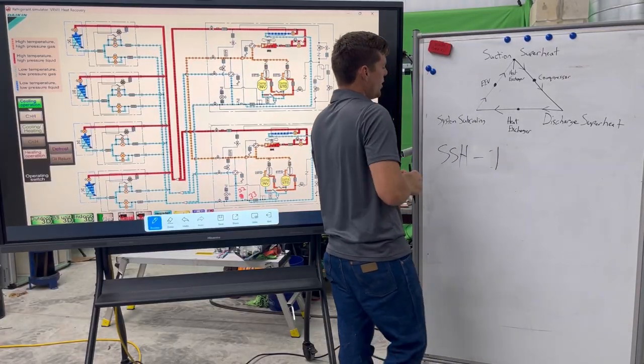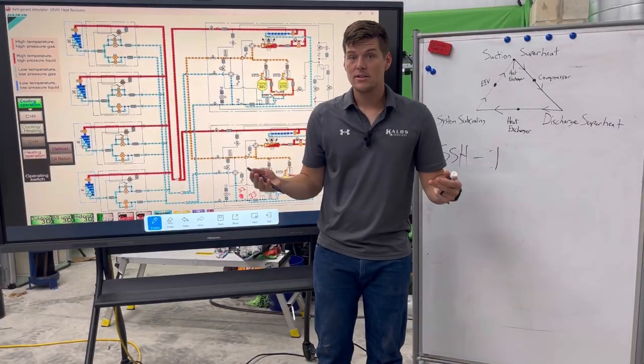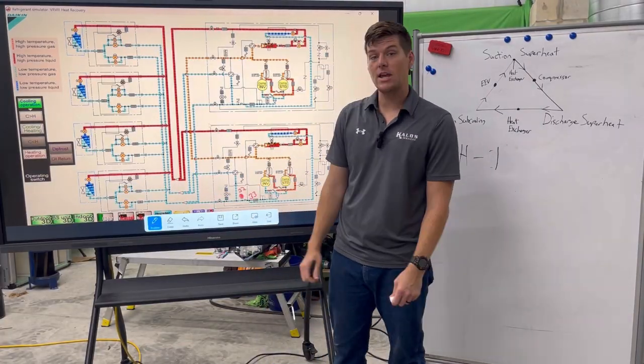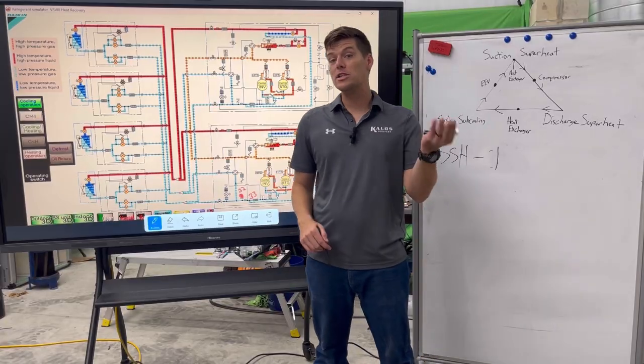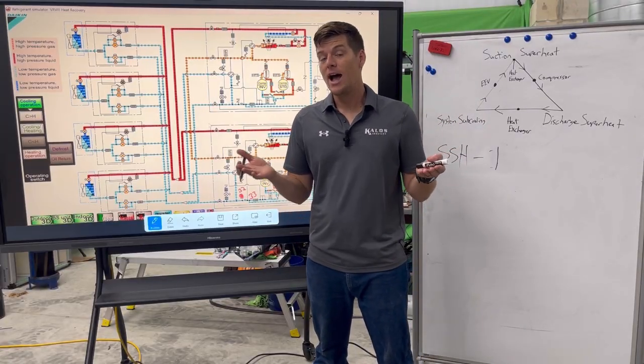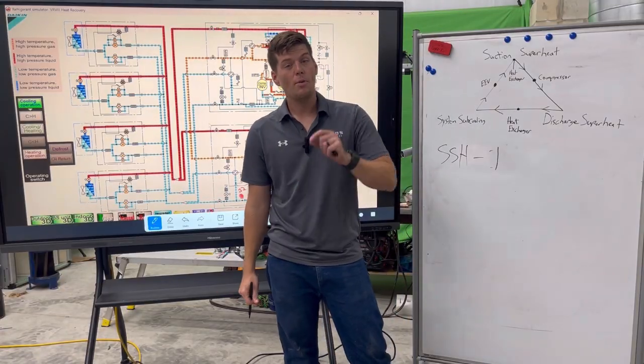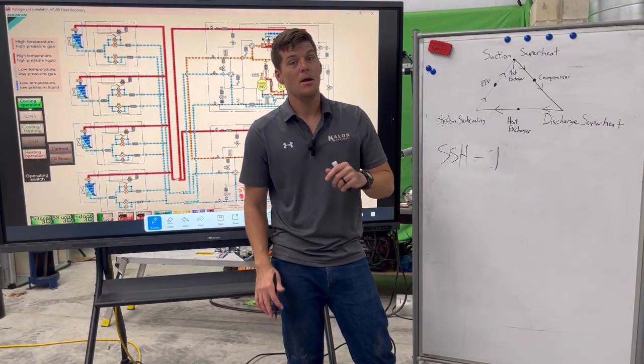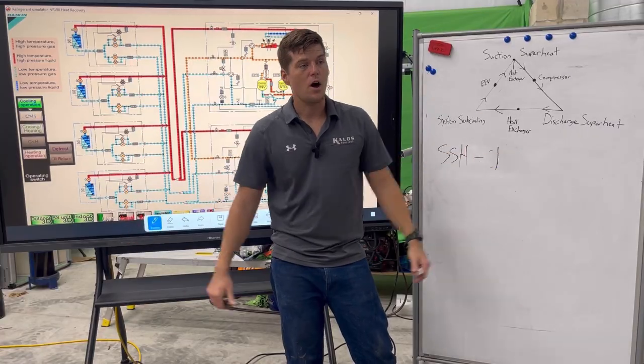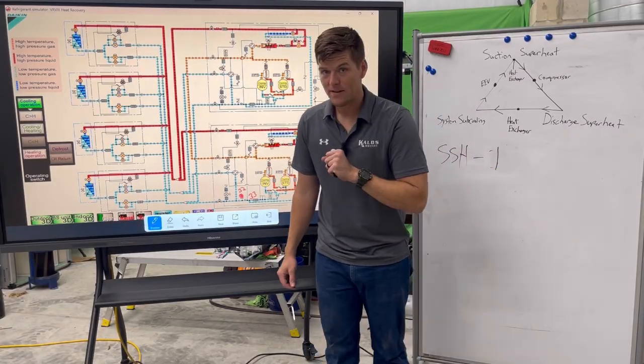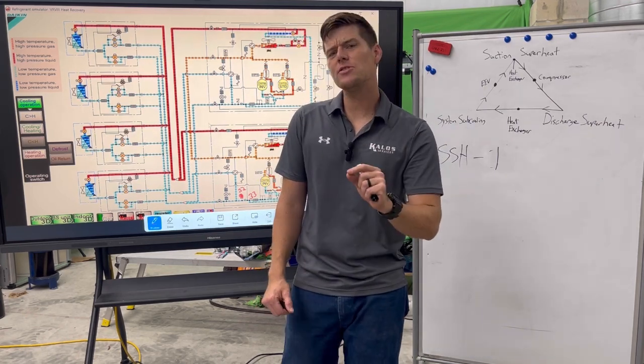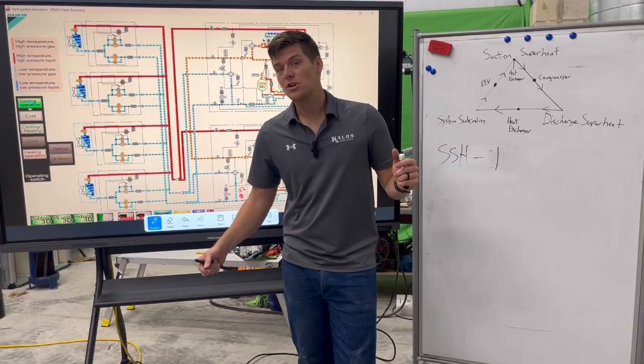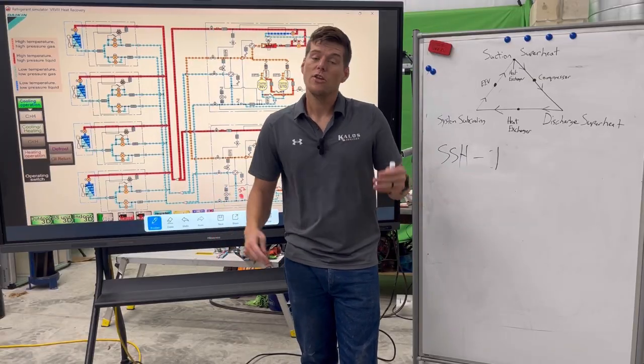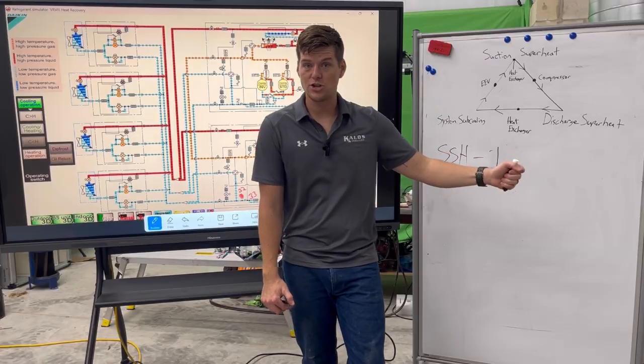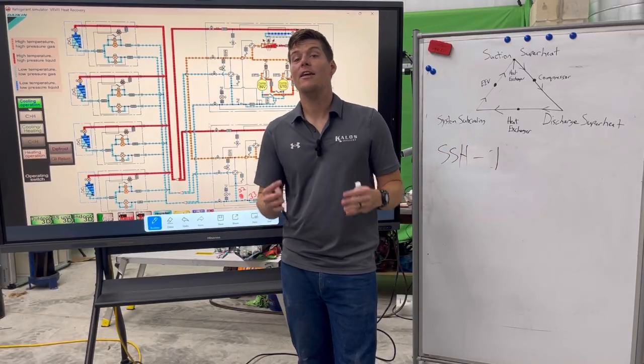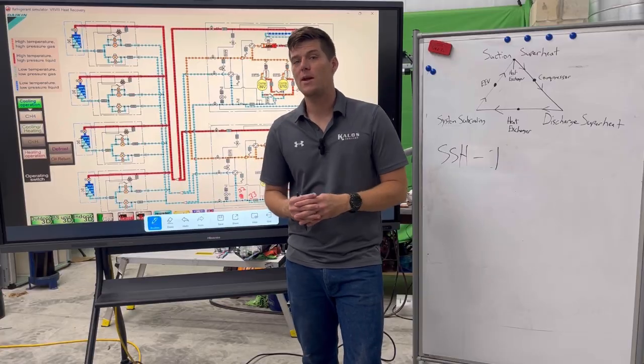Well, what do we know about 1 degree of suction superheat? The closer we get to saturation of 32 degrees, remember this is a pressure sensor that is determining at this pressure what the actual saturation temperature is, I know that I'm 1 degree above saturation. Being 1 degree above saturation means I am 1 degree from becoming 100% liquid. Now, you're going to say, well, 1 degree is still superheat. And it is superheated. But how much of that is vapor and how much of that is liquid? Is it a mixture? Is it a slurry? And the answer is yes, it is. The closer we get to saturation, the higher the concentration gets of liquid within that suction line, right? Within that vapor line, because that's what it is. It's supposed to be 100% vapor in that line at all times.